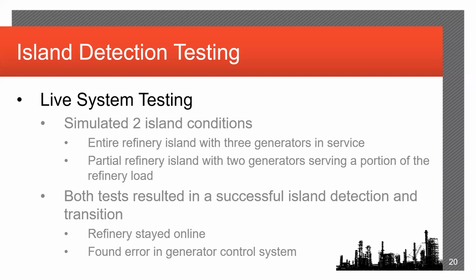And there was a bit of a glitch in that particular test because there was some configuration or programming inside of the turbine generator controls that was not set up quite right. But the system did 2 things. It did detect that the refinery was islanded, and did send the correct signals over to the turbine generator controls. After that was fixed, we ran another test where we islanded part of the refinery with 2 generators, and that particular test came through with flying colors. The generators changed control modes, and that partial refinery island stayed energized with no hiccups in the middle.